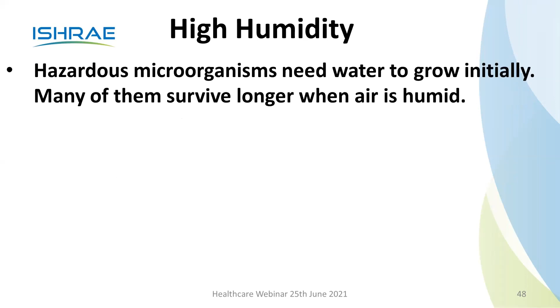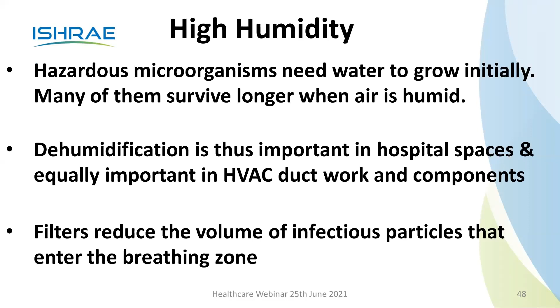But if you have high humidity on the other side, hazardous microorganisms need water to grow initially. Many of them survive longer when the air is humid. Dehumidification is thus important in hospital spaces and equally important in HVAC ducts and components. Filters reduce the volume of infectious particles that enter the breathing zone. Humidification helps the body resist infectious particles not trapped in the filters. Then dehumidification reduces the number of particles that exist in the first place. So that means you need to be somewhere in between. You should not have high humidity or low humidity.